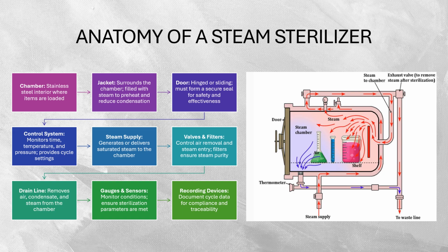The anatomy. This is important. We have to know the anatomy of the sterilizer, what the components are used in the high temperature sterilization process. The main one is the chamber. This is the main area for item placement. It's surrounded by a steam-filled jacket to maintain the optimum conditions. The chamber is the big portion of the autoclave. This is where we're putting the devices once they are on the autoclave cart; that rack gets pushed into the chamber. And this chamber is surrounded by a jacket.